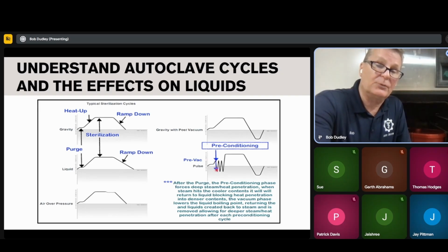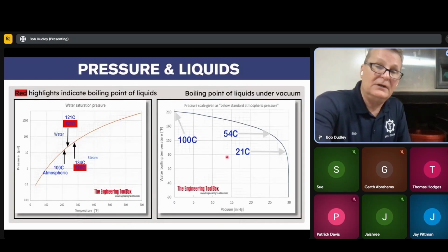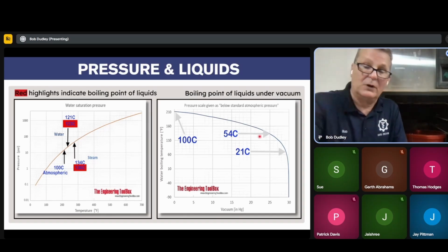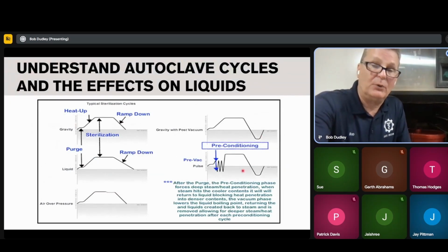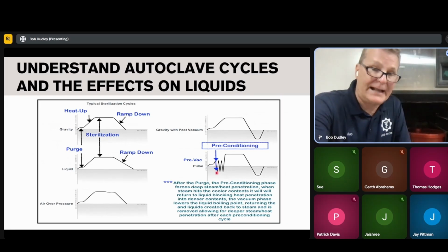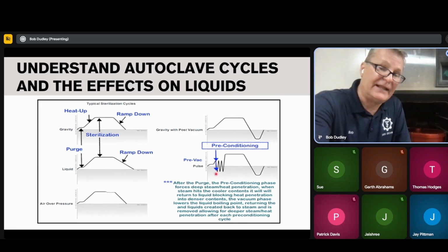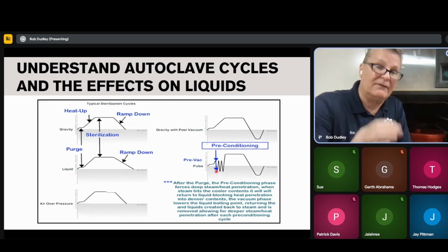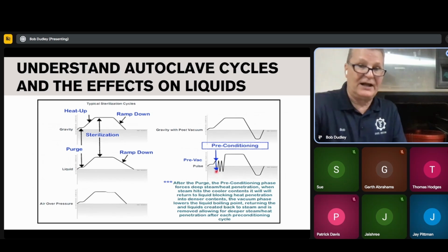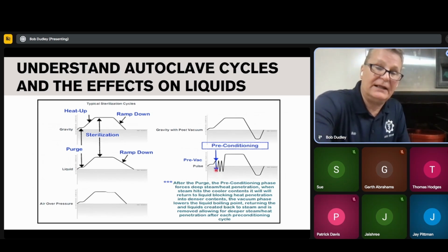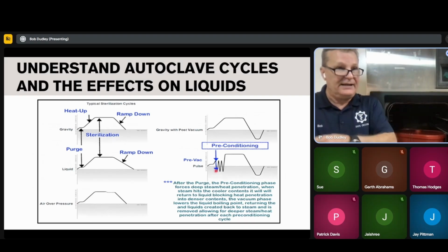But what happens? You're going to pull that vacuum. So now, you've pushed it into 10 psi. You're right there at 115 degrees. You've got that block. You pull a 25-inch vacuum, and now that temperature of that liquid is again 54, 129, and of course that's the boiling point. And what happens? It turns back into gas. It has just eliminated that block, that liquid block that happened here. Now, when you pull that vacuum, all that liquid that was getting in the way of that penetration that stopped it is now gone. Now it's turned back into gas, and then with the pre-vac, it opens up the pump.